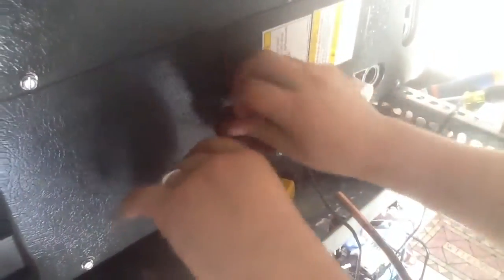You see how he's got two nice shiny ends? Now he's going to take his sandpaper and just kind of brush the inside of these two and brush the outside on both of these — both the liquid and the suction line. Just ever so lightly is all he's going to do, just make sure there's no oil around the edges. This preparation work is very, very important — it has to be done.